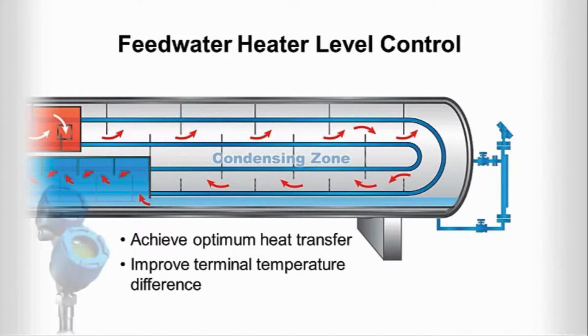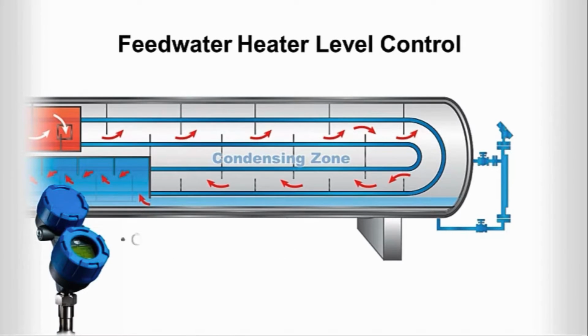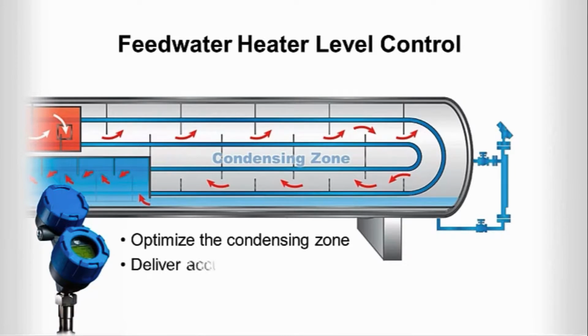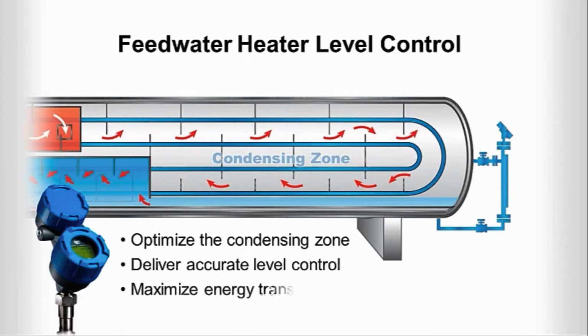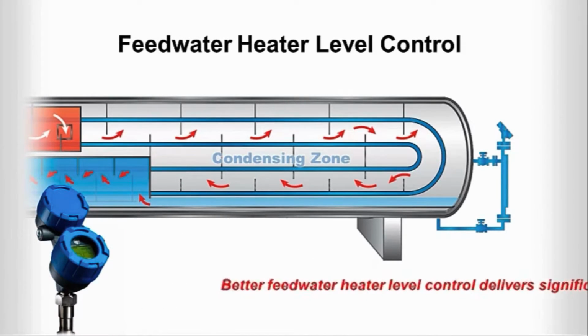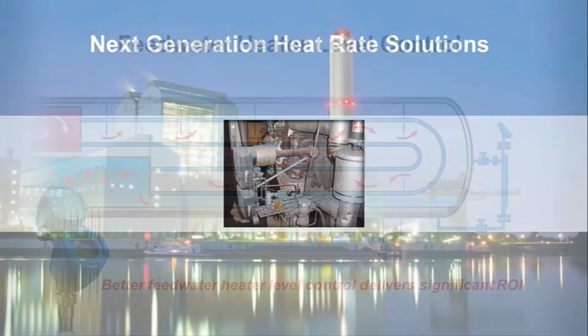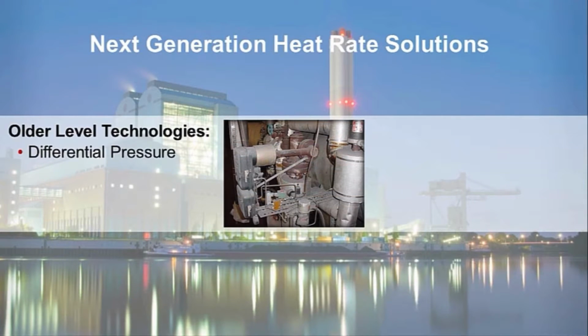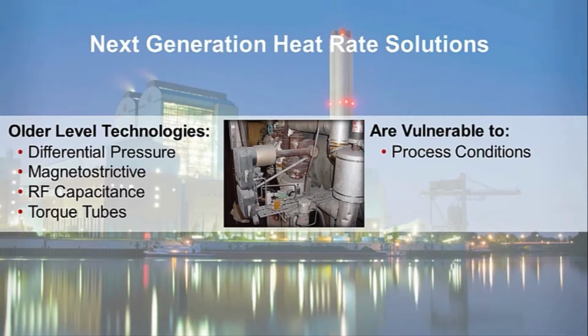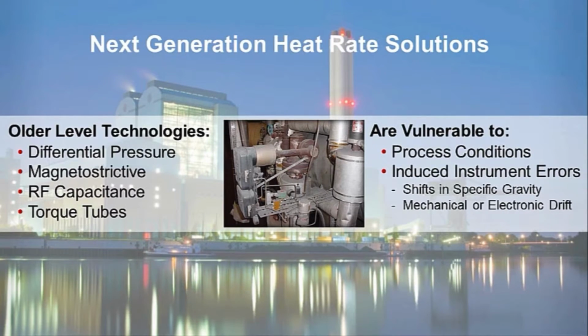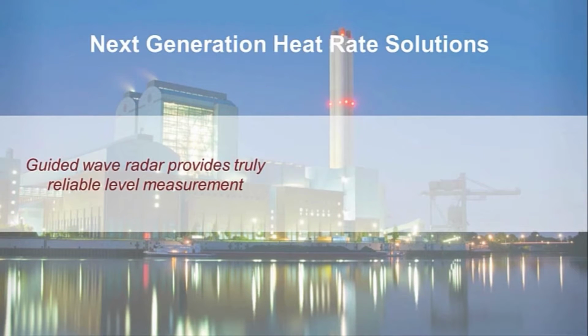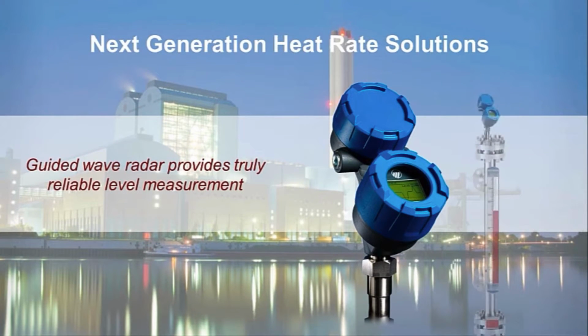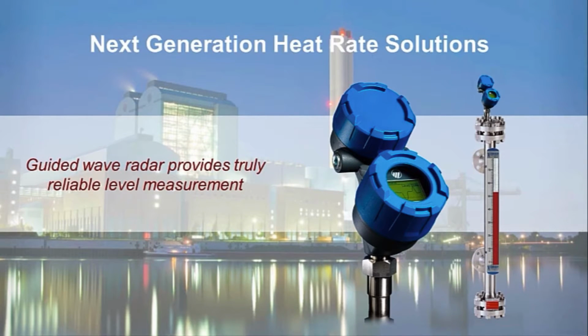With Eclipse Model 706 guided wave radar, you can optimize the condensing zone of your feedwater heater to deliver accurate level control, maximize energy transfer, and minimize undue wear and tear. This can help you generate the savings needed to recover your investment. Older level technologies, such as differential pressure, magnetostrictive, RF capacitance, and torque tubes, are vulnerable to process conditions and induced instrument errors, such as shifts in specific gravity and mechanical or electronic drift. In contrast, guided wave radar provides a truly reliable level measurement solution for feedwater heaters.